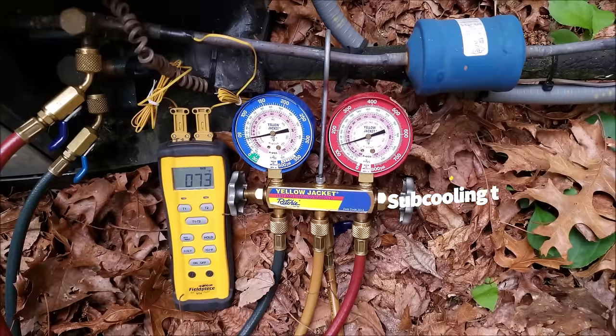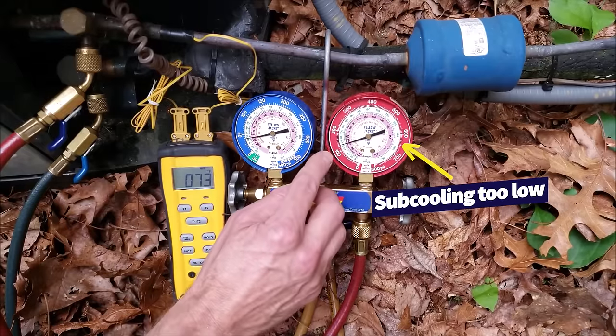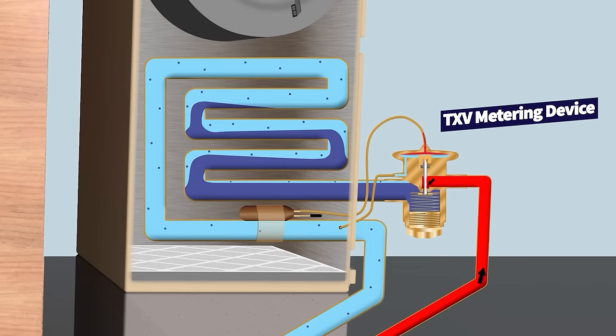If you are low on refrigerant, that means you have a leak on your air conditioning system which may have occurred at a joint or some corrosion point, and that leak is going to need to be addressed. But you can't just assume that you're low on refrigerant, because you could also have a problem with the restriction device restricting the refrigerant charge too much because it's broken.